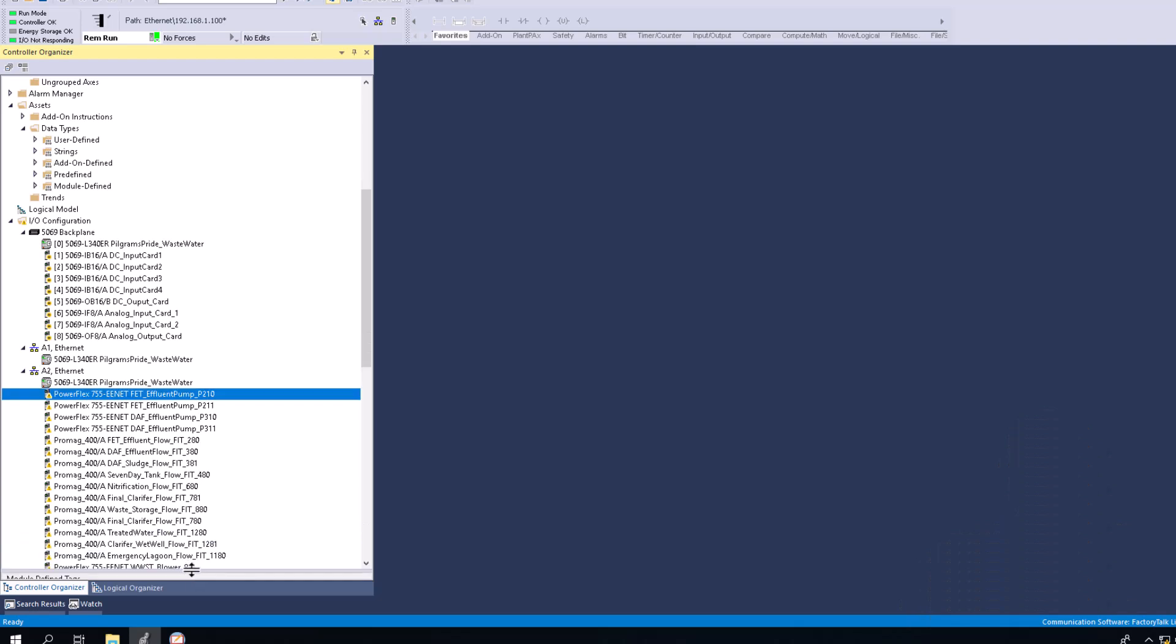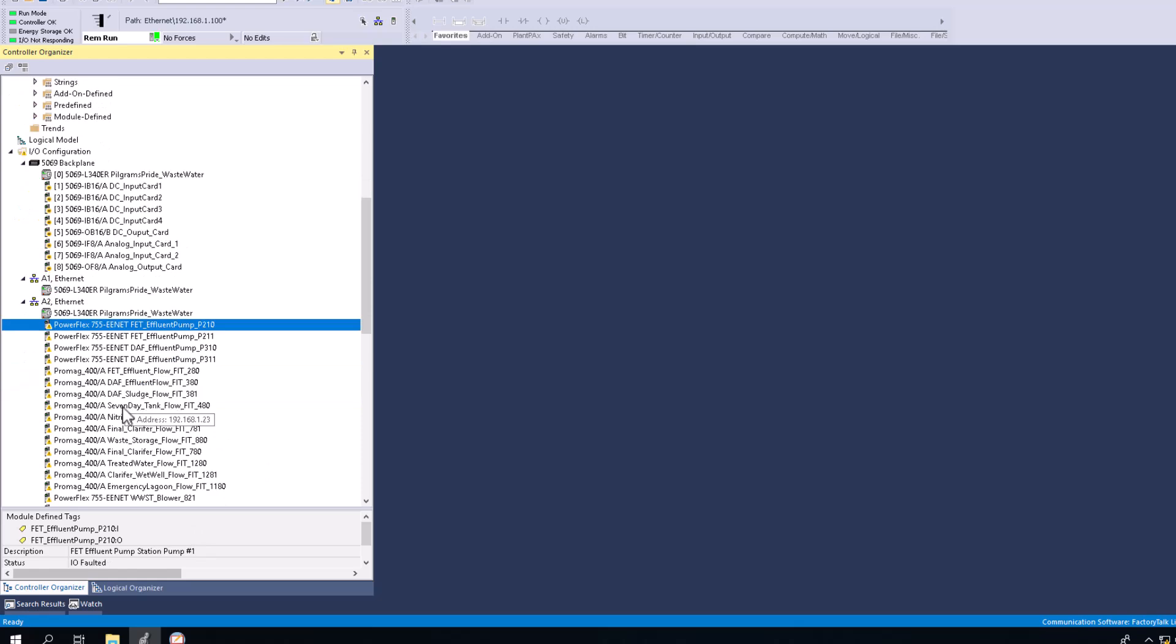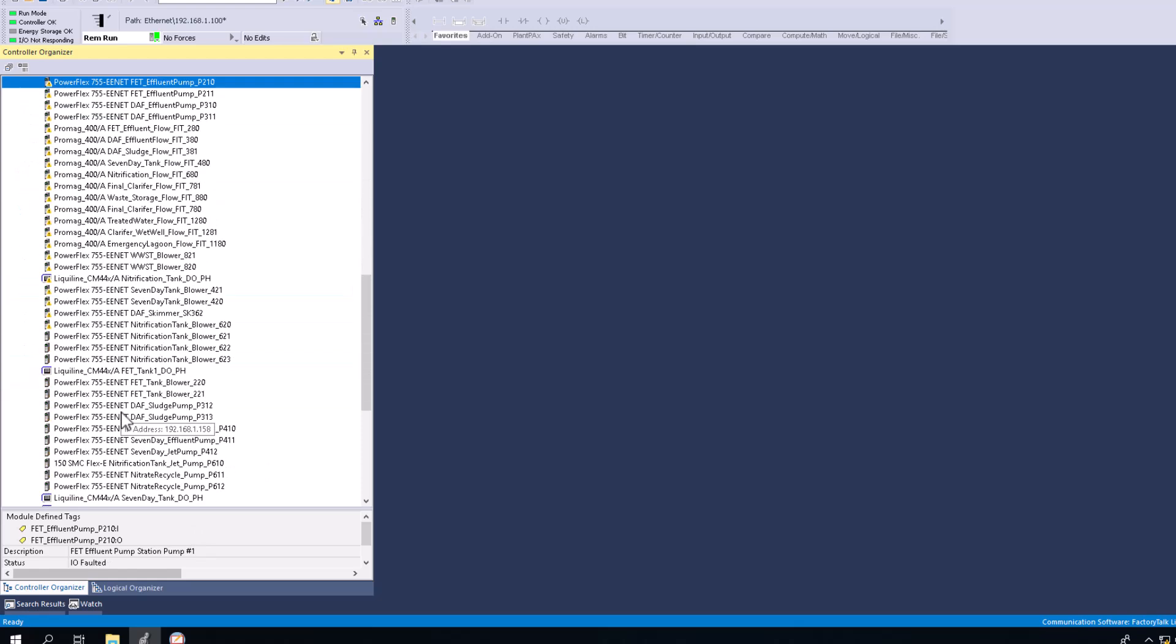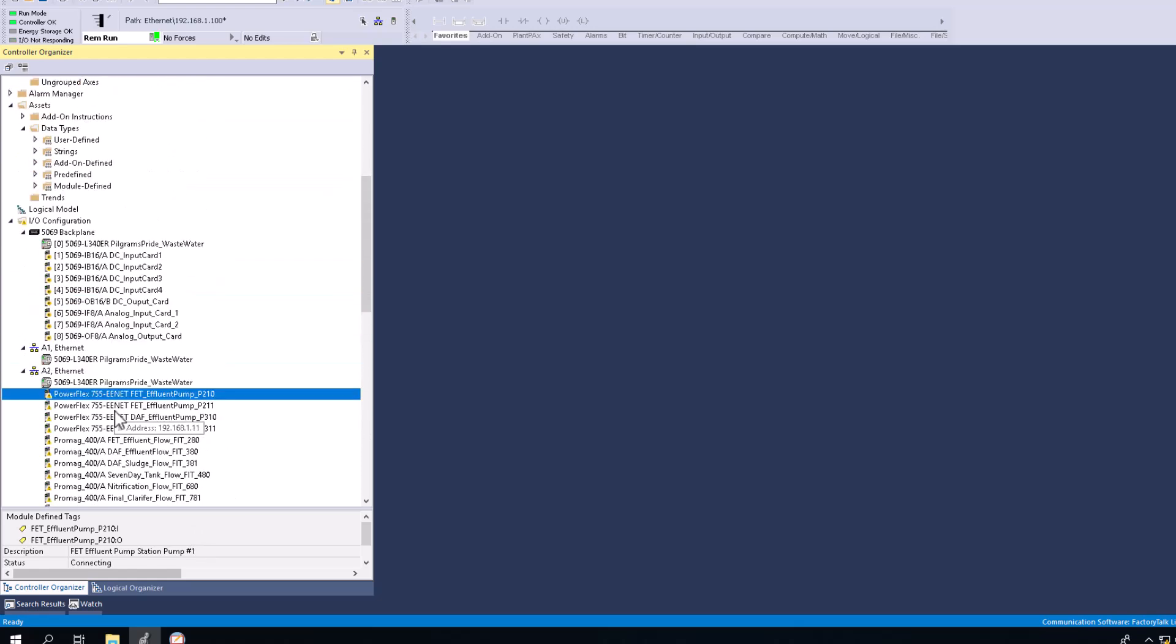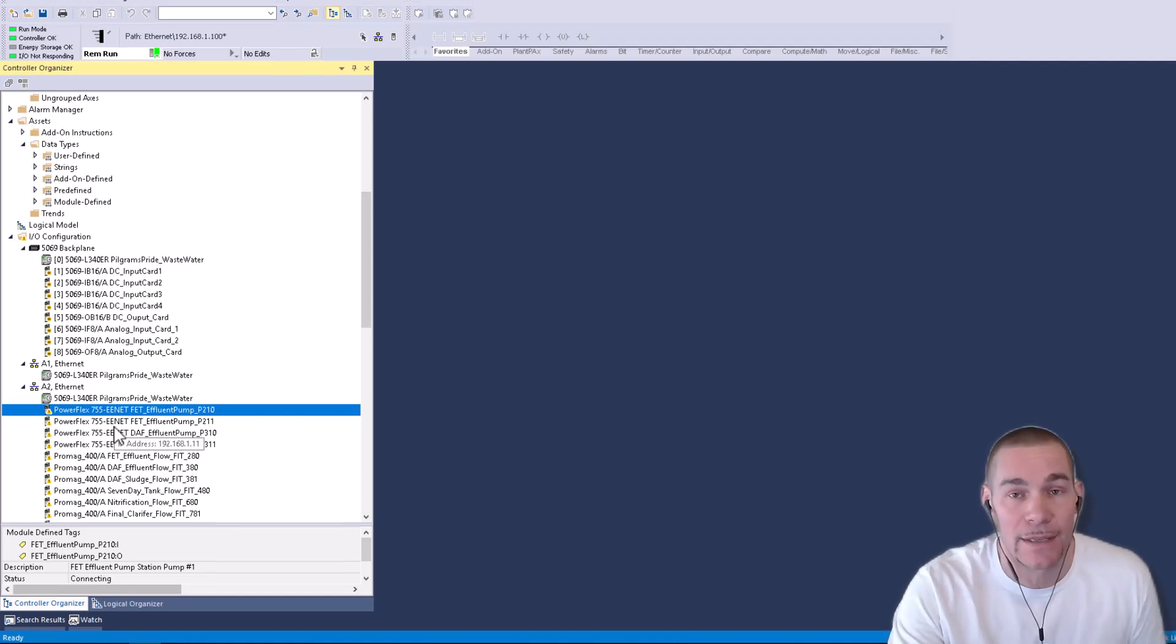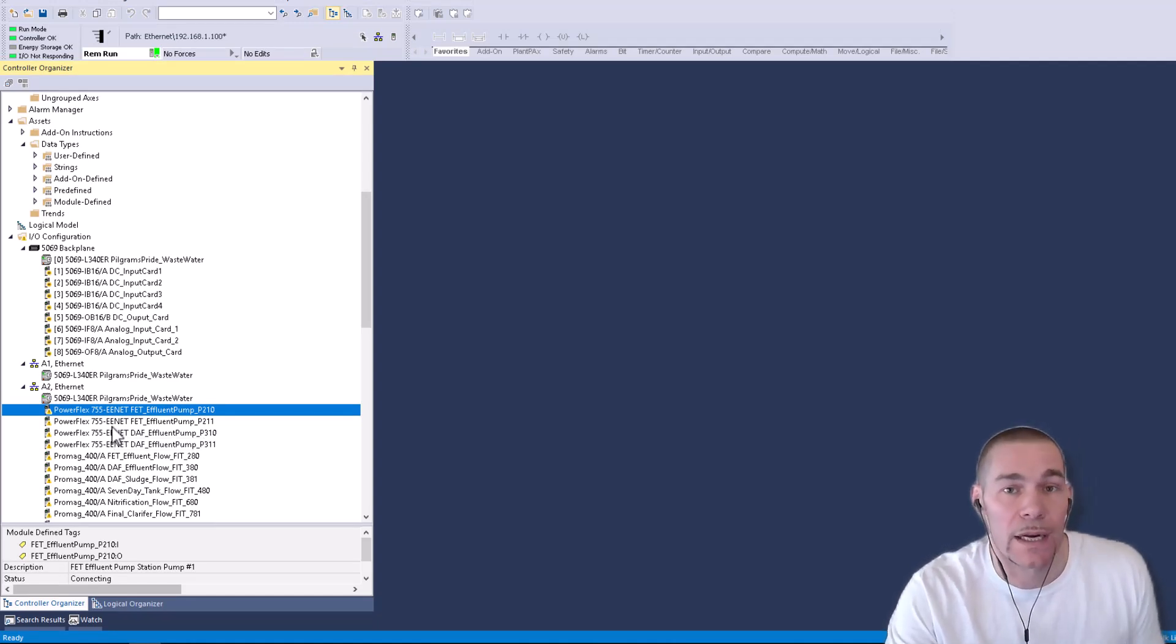So what I like to do is by default just pull it up. And that way I can tell, and generally if everything is healthy in your IO tree you won't have a problem, but just like in this instance right here, I'm showing that the IO is not actually healthy.